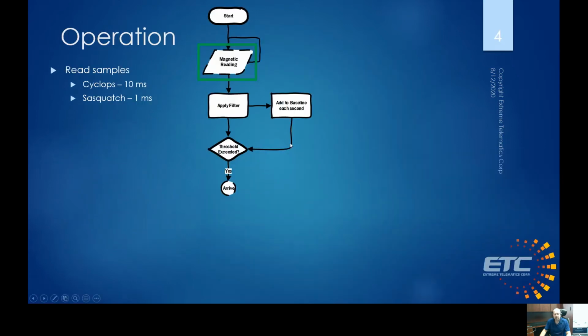In terms of the operation internal to the sensor, getting a little bit more detailed, we read samples every 10 milliseconds on the Cyclops and 1 millisecond on the Sasquatch. We need that higher resolution on the velocity sensor because the plunger can be moving very quickly as it goes by the sensor. We do apply this filter, so we take an average of 3 samples to get rid of the high frequency noise. And then every second, we're taking these filtered samples and we're coming up with the baseline.